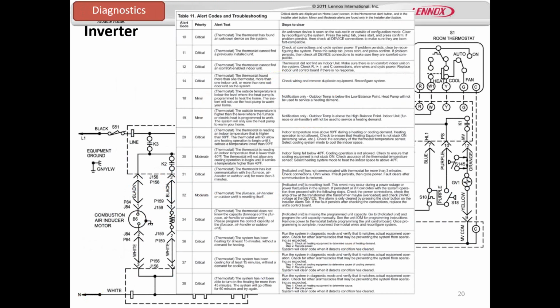The inverter itself has blinking lights. It also can read back to the board. You'll have a different set of codes on the outdoor unit versus what you get inside. There is a conversion tool for that. If you put this in, it's going to tell you, in that tool that I told you about on Lennox Pros, it will convert that over to what the actual code would be on the control itself, the thermostat. Generally speaking, we don't have any way to generate 3 blinks, 3 light codes. We have 2 lights in the inverter itself, and so it blinks a light and generates a 2-digit code. So we have to convert those differently.